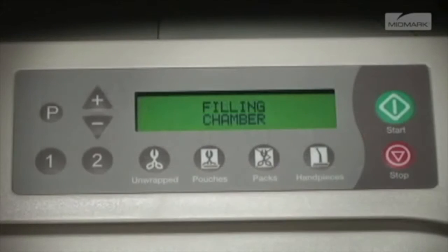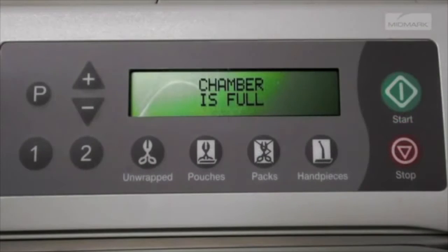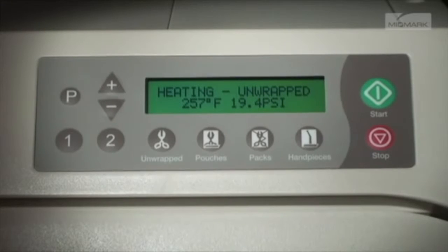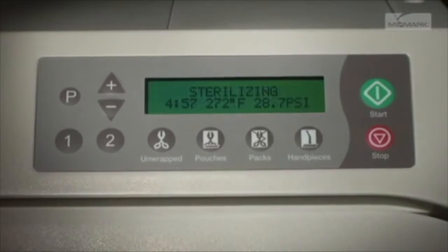The display immediately shows the message, Filling Chamber, followed by Chamber is full, when the proper water level is reached. Now, the unit will begin to heat to the appropriate temperature for the cycle being used. The display changes as temperature and pressure in the chamber changes. Once the appropriate sterilizing temperature is reached, the display shows the time countdown from the programmed time and monitors the temperature and pressure. During sterilization mode, the heater will cycle on and off.